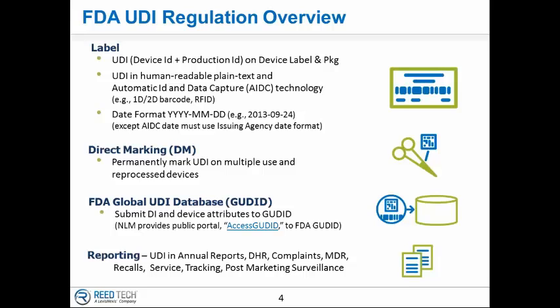So Ryan follows up. So this is a format for dates, not a mandate for dates on the label beyond current FDA requirements? Great point, and I neglected to mention that as we walked through. So all those production identifiers, even a serial number, a batch number, and so on: the FDA rule says that if you don't have them now on your label, you do not have to add them. It doesn't require adding those particular elements to your label. But the final rule goes on to say, if you are currently using those for production control, and it's on your label, then you do have to flag that information and report that to the FDA.